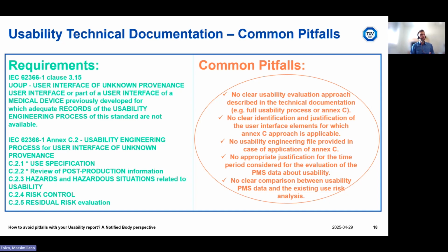Step 4, the manufacturer has to confirm that the implemented risk control measures related to usability and to the use of the device are complete and appropriate. Last step, overall residual risk evaluation has to be performed again. Common pitfalls. No clear usability evaluation approach described in the technical documentation.